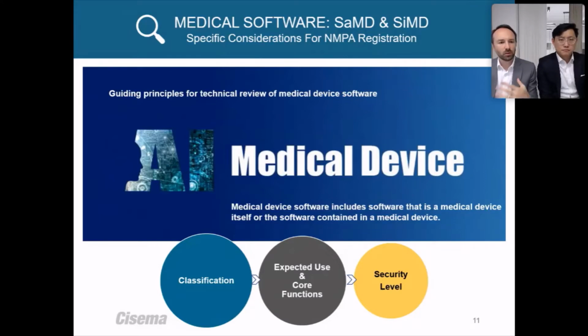Secondly, NMPA will encourage manufacturers to consider the expected use scenarios and core functions of software products so as to carry out corresponding risk management activities. And finally, we need to consider the security level of software products in the life cycle. In recent years, NMPA's software audit is more and more standardized and rigorous. In particular, the test verification and validation in the software description file, as well as the review of software versioning and software updates, etc. In the description of software network security, the review of network capability, security update, maintenance, and emergency response plan is particularly strict.